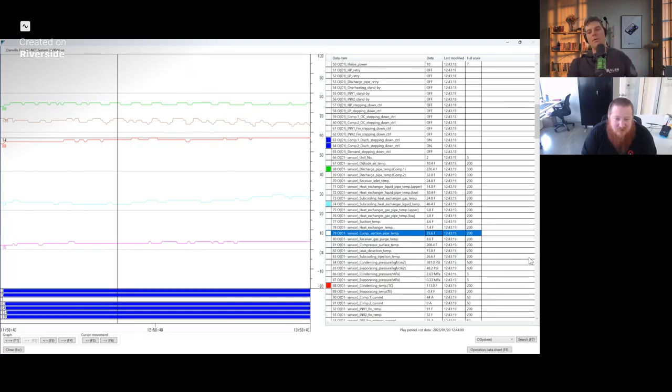It's important to remember when systems are low on charge, extremely critical charge, really, really low, and still continuing to operate in extreme conditions, because again, we're 10 degrees outside. You have to remember that at certain points, you have to ask the question, is it a liquid or is it a vapor? And again, we would say that it is a vapor or it's somewhat changing states as it goes.